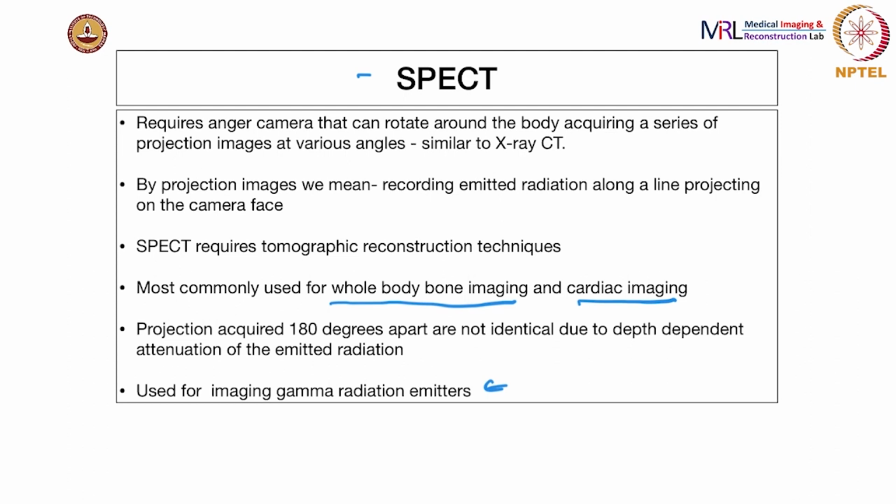If you think of the collimators as a cylinder, whatever is confined in that straight cylinder is what you image. You do that at every angle, and then you can model the underlying activity as a kind of line integral, and do the reconstruction very similar to back projection.